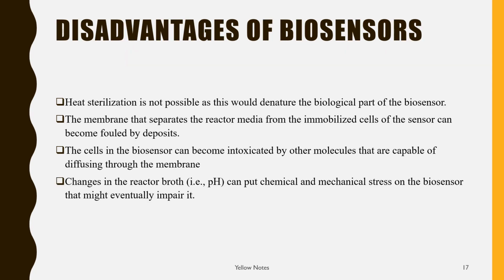Now there are certain limitations or disadvantages of biosensors. The first one is that heat sterilization is not possible as this can denature the biological part of the biosensor. Second, the membrane that separates the reactor media from the immobilized cells of the sensor can become fouled by deposits. The third one is that the cells in the biosensor can become intoxicated by other molecules that are capable of diffusing through the membrane. And last, the changes in the reactor broth can put chemical and mechanical stress on the biosensor that might eventually impair it.